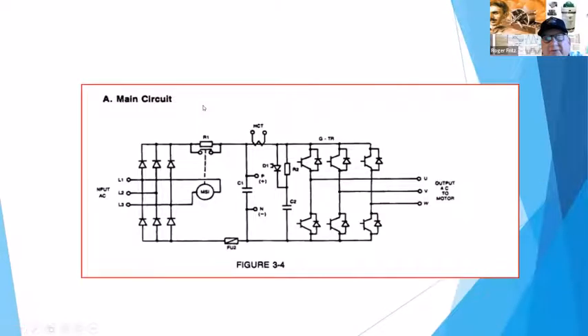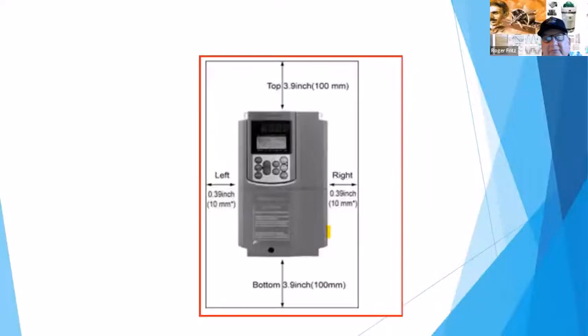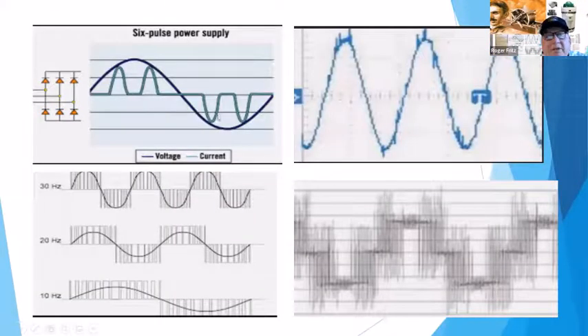I'm going to go to another picture. I'll go back to those further. I guess I won't, so I'll discuss that a little bit later. But the issue is that this actually creates some ripple, and it also affects the voltage. That's why they came out with the IEEE 519 harmonic requirements for applications, because this is a look at a waveform of the input after it's had multiple drives supplied to its circuit, and all other solid state devices in a plant.